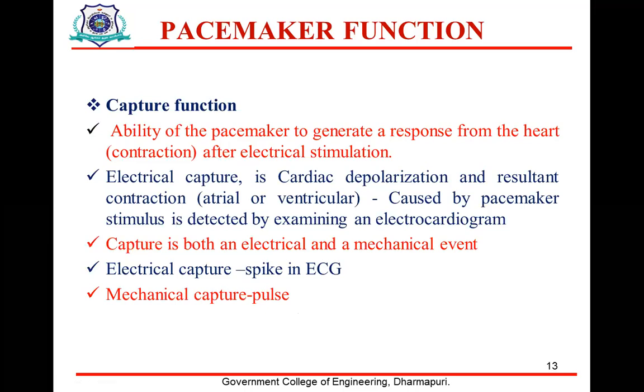The third function is the capture function, the ability of the pacemaker to generate a response from the heart after electrical stimulation. Electrical capture is a cardiac depolarization, and the resultant contraction caused by the pacemaker stimulus is detected by examining the electrocardiogram. Capture is both an electrical and a mechanical event. For electrical capture, it is a spike in the ECG, and for mechanical capture, it is a pulse.